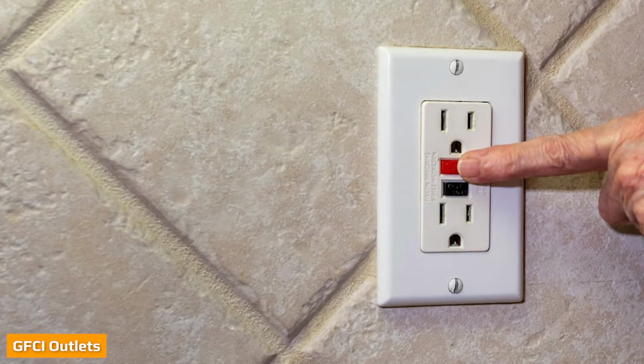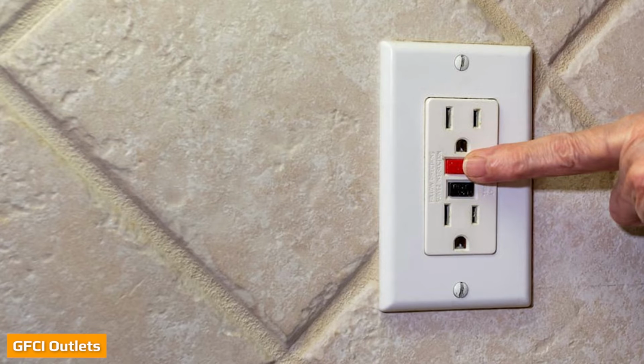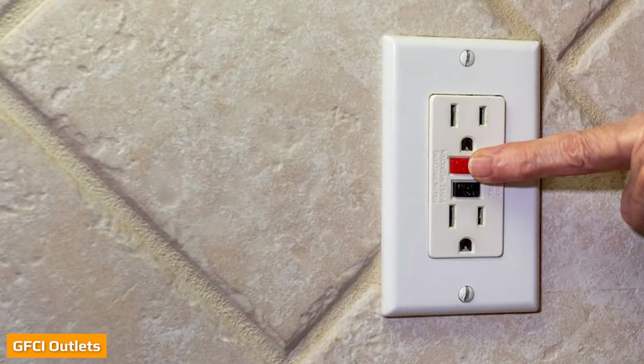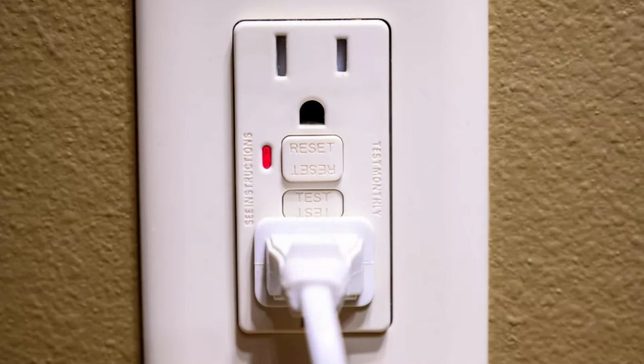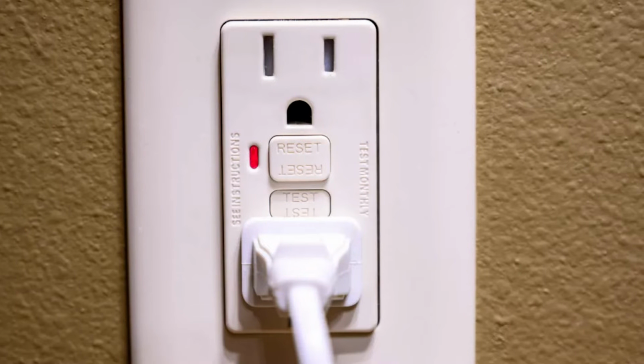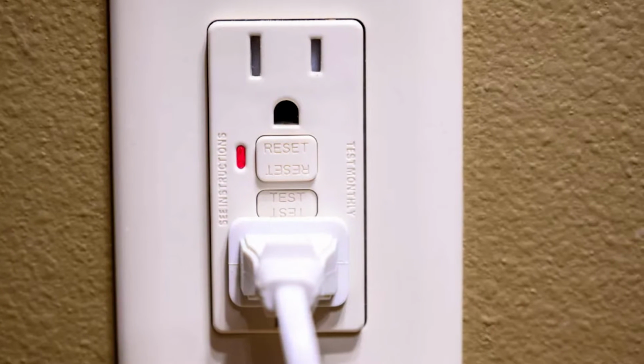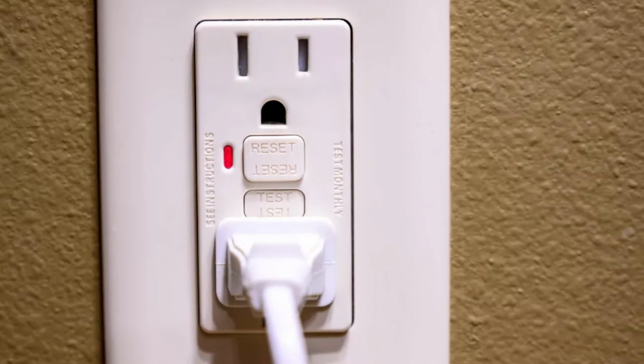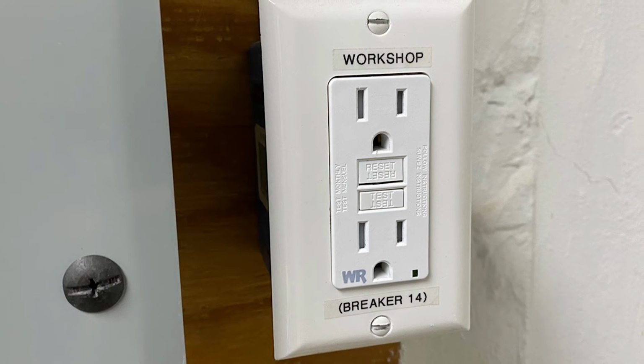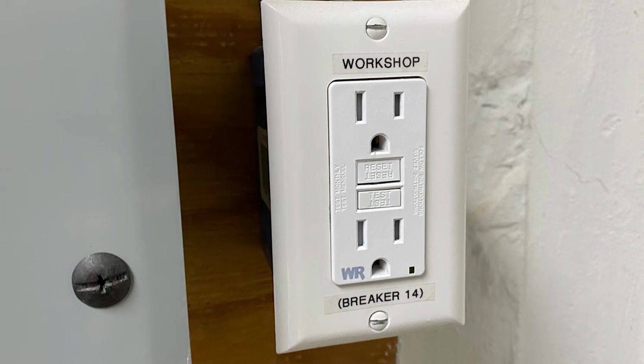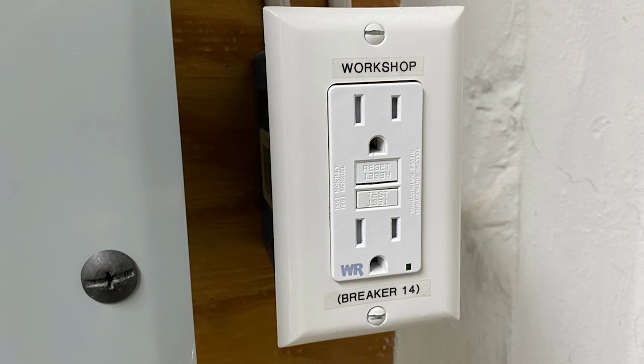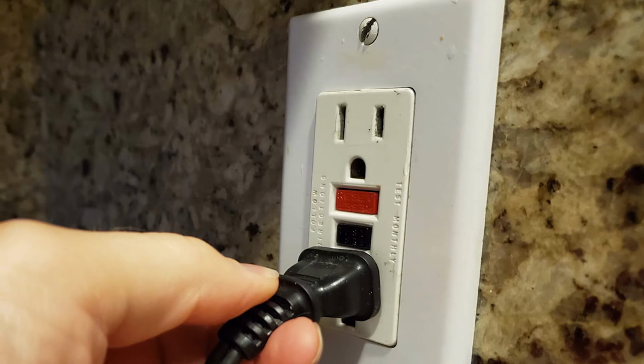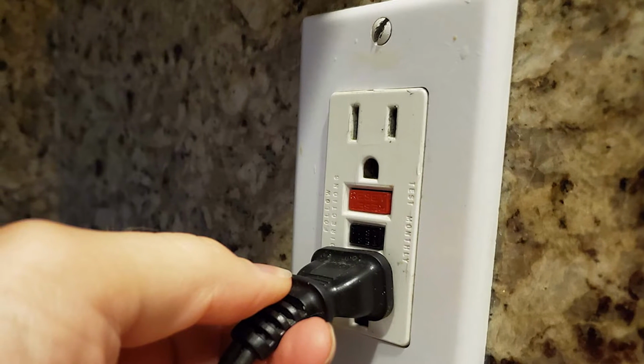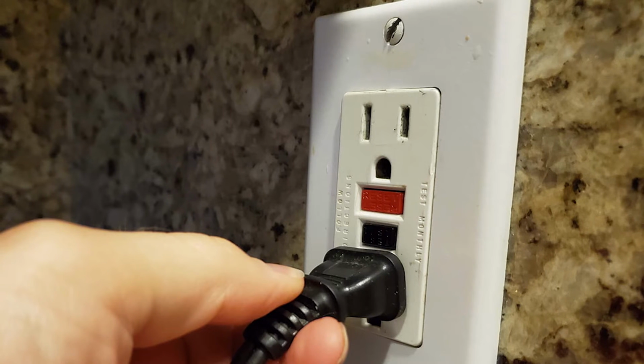Line and load have special meaning when wiring ground fault circuit interrupter, GFCI, outlets. GFCIs have two pairs of screw terminals for connecting wires. One pair is marked line, and one is marked load. Connecting to the line terminals only results in the outlet providing GFCI protection only for that outlet. Connecting to both the line and the load terminals, using two electrical cables or two sets of pigtail wires, provides GFCI protection for that outlet as well as for other standard outlets located downstream on the same circuit.